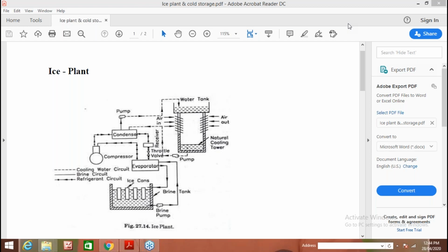It also has better thermal properties than F12, and its cost is almost 10% less than F12, and we require much refrigerant, so cost makes the difference between F12 and ammonia. And sodium chloride is generally used as brine because it is less injurious as well as its cost is very less.